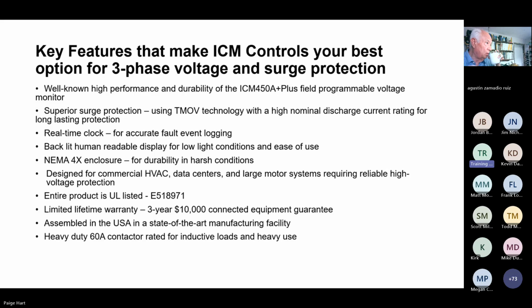It also incorporates a heavy duty 60 amp contactor rated for inductive loads and heavy use, much different than some of our competitors' products that only use block relays that may be rated for inductive loads, but not for heavy use. For example, this contactor can withstand up to 250,000 cycles, whereas a block relay may only be able to withstand 5,000 cycles. So this is meant for heavy duty abuse.